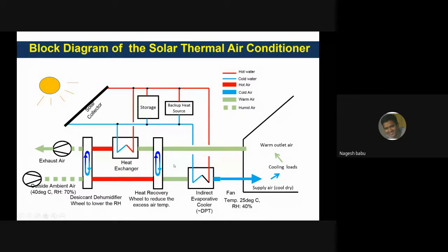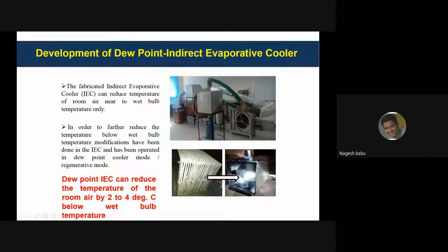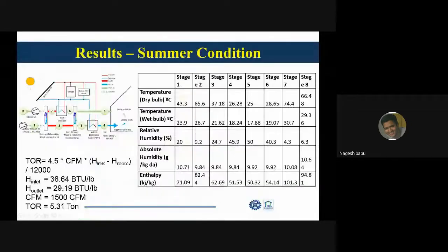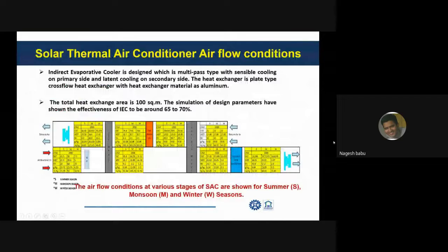This particular indirect evaporative cooler, what I have discussed until now, will be the actual cooling mechanism happening. However, how do we reduce the humidity? In order to reduce the humidity, we will be using a desiccant dehumidifier, and we have been experimenting on this facility and have achieved room temperatures even below the wet bulb temperature by 2 to 4 degrees centigrade. Wet bulb temperature is a very comfortable room temperature, and we can reduce the temperature 2 to 4 degrees centigrade below the wet bulb temperature also. These are various results in which we have reduced the temperature below the wet bulb temperatures. And this is a typical solar thermal air conditioner's airflow simulation. Here also we have reduced the temperatures below wet bulb temperatures.